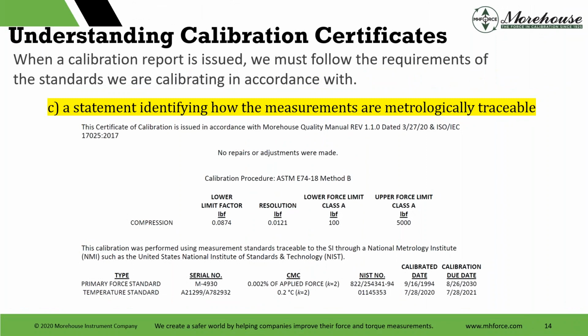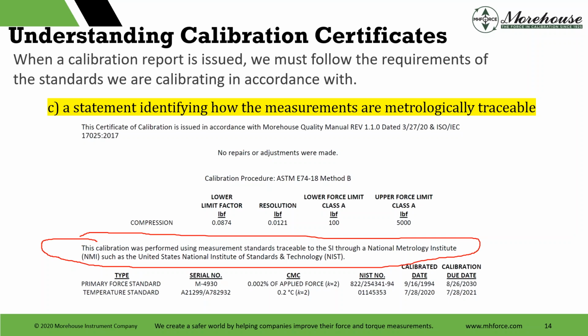So we've dealt with measurement uncertainty and how that works. Now we're going to start dealing with the calibration report. When a calibration report is issued, we must follow the requirements of the standards we are calibrating in accordance with. And we go back to ISO IEC 17025, a statement identifying how measurements are metrologically traceable. So here, we look at this: this calibration was performed using measurement standards traceable to SI through a National Metrology Institute, NMI, such as the United States National Institute of Standards and Technology.